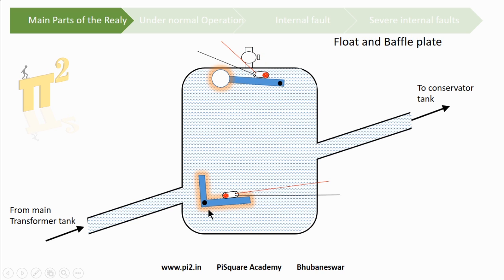Here is a float and a baffle plate. There are two mercury switches - one connected to the alarm circuit and another to the trip circuit. These mercury switches play a key role in activating the alarm as well as the trip circuits.